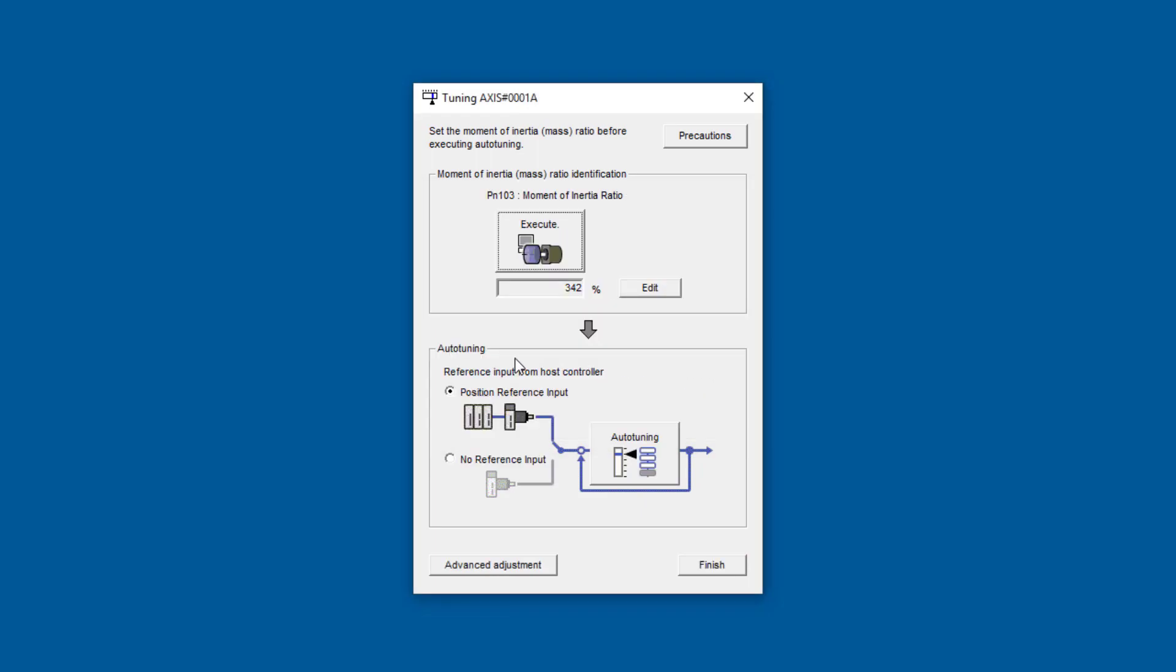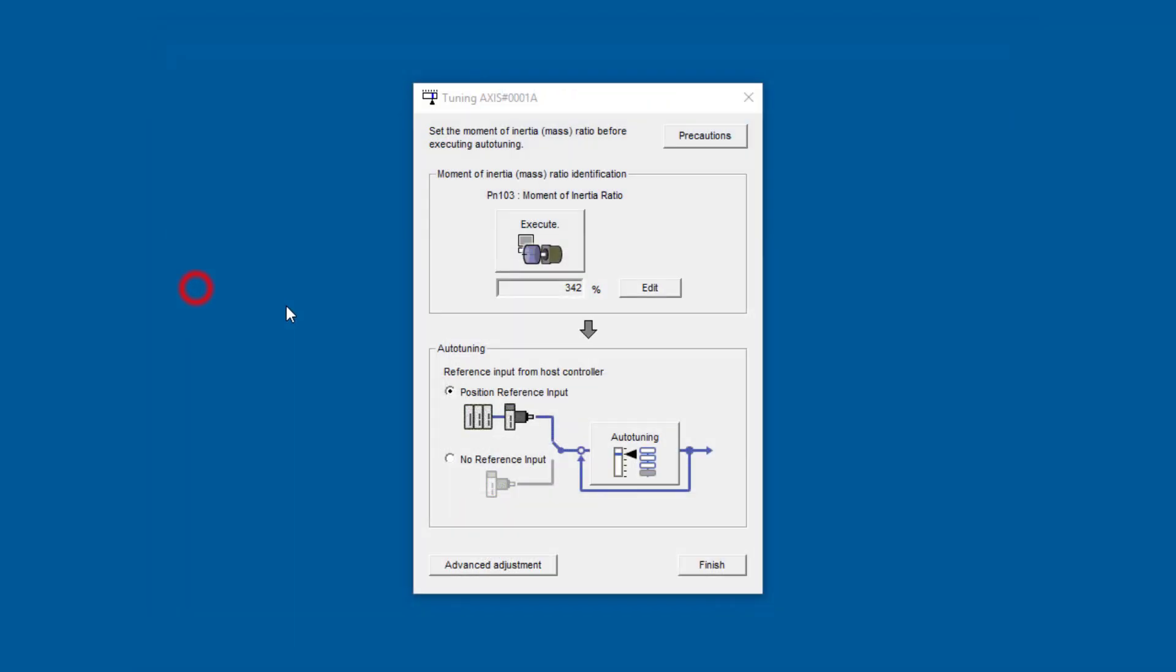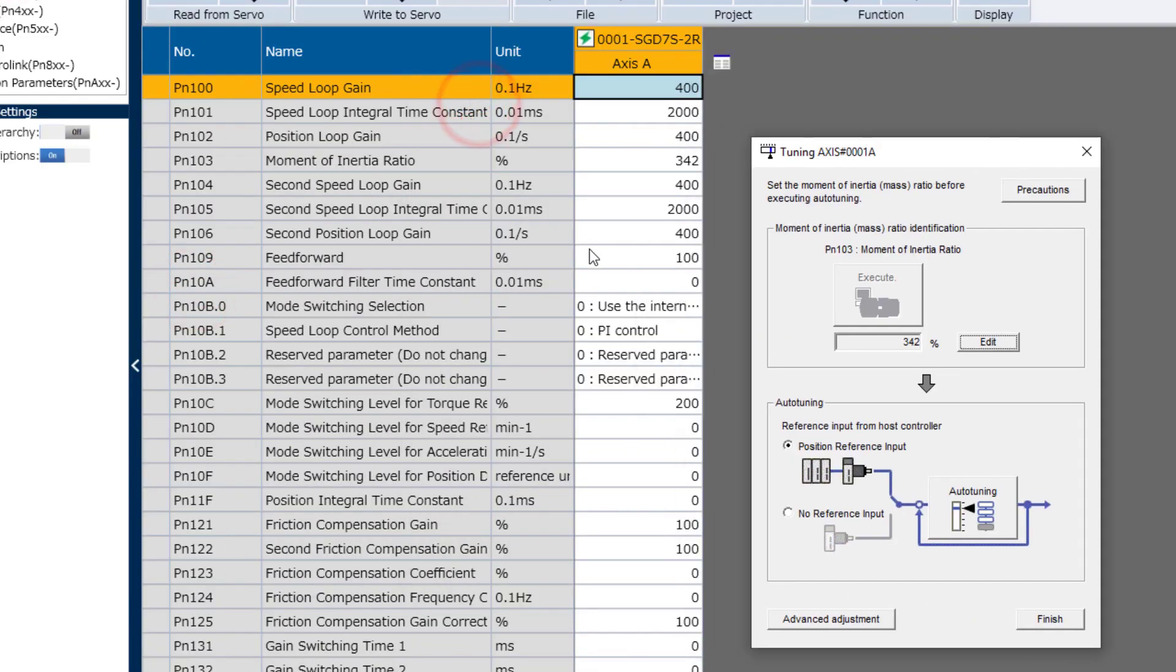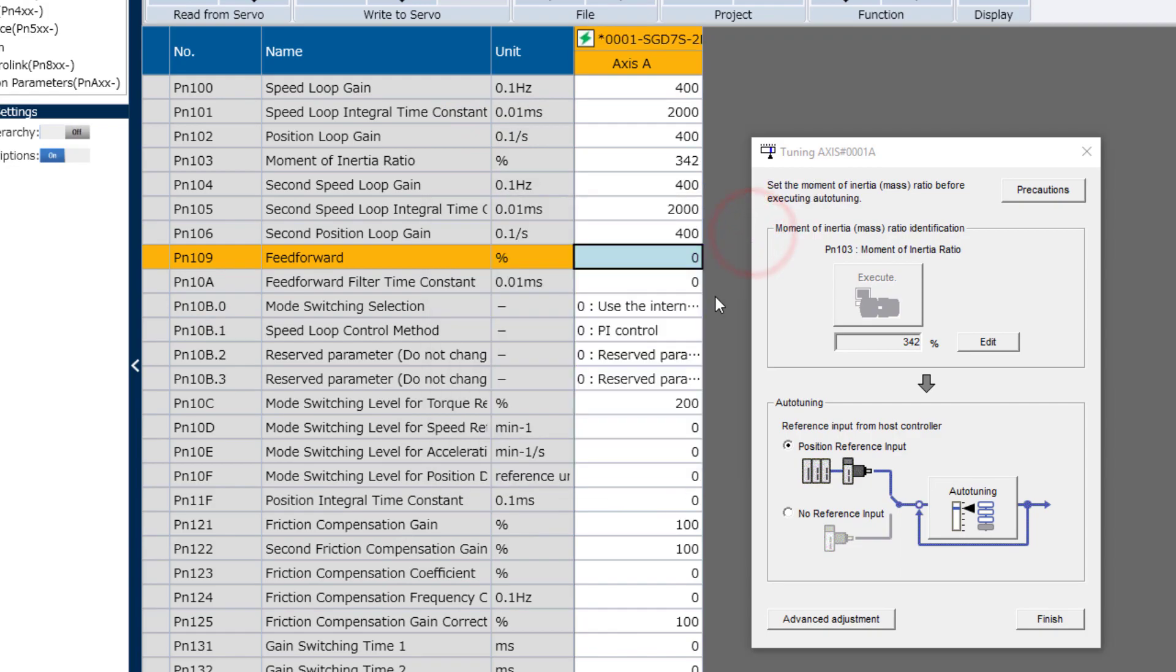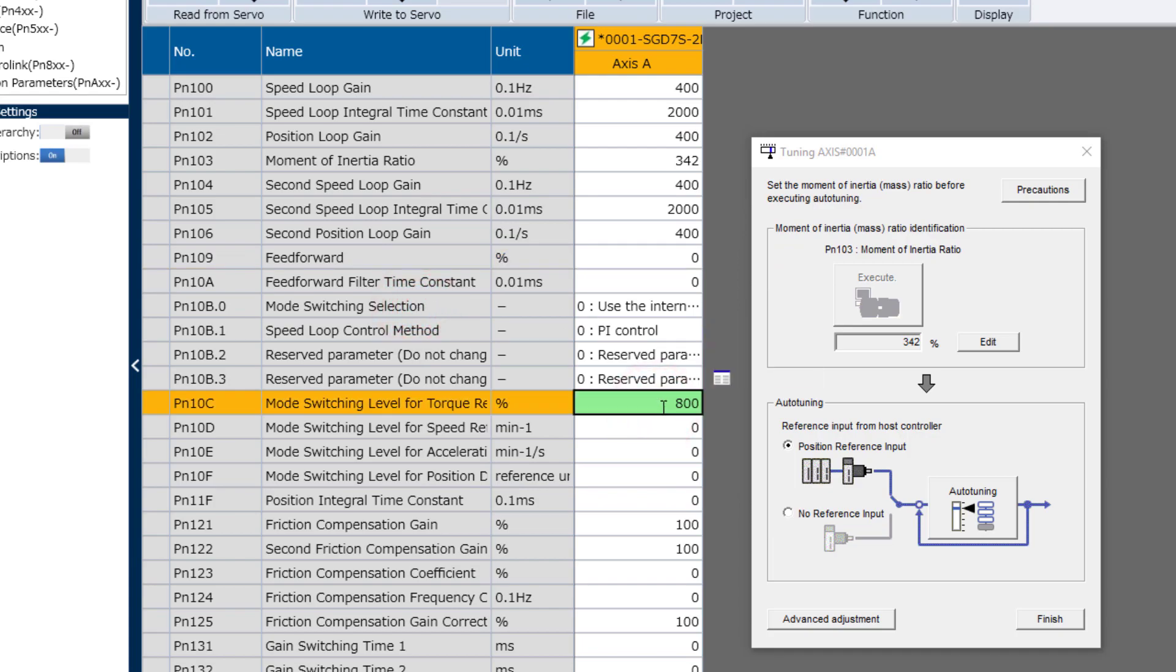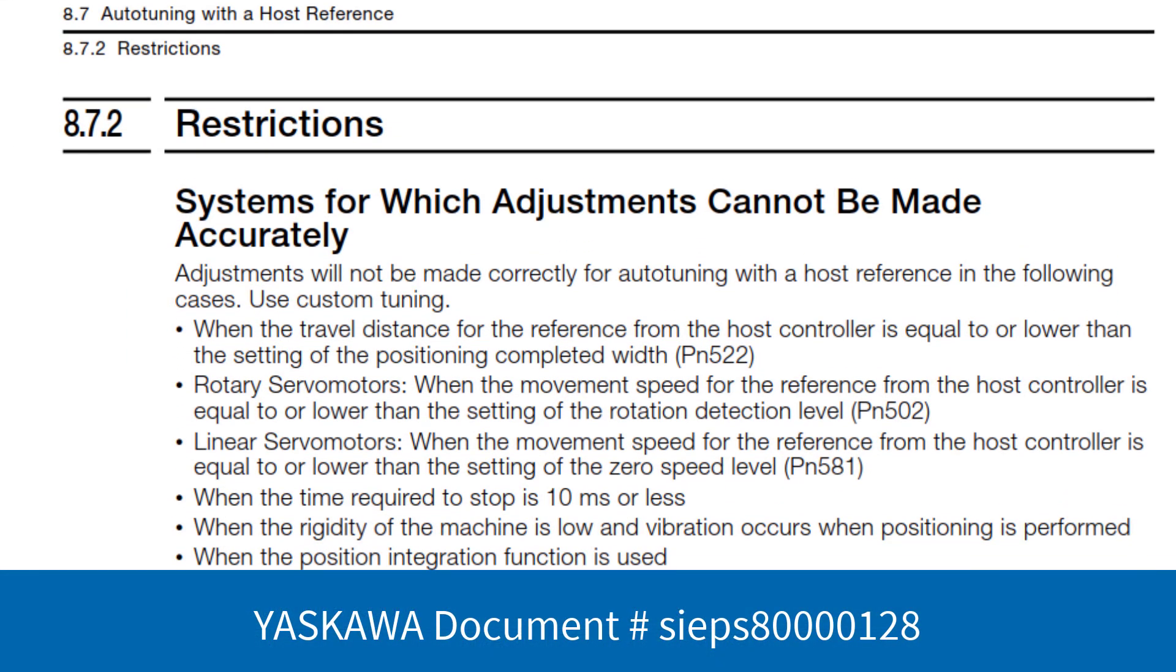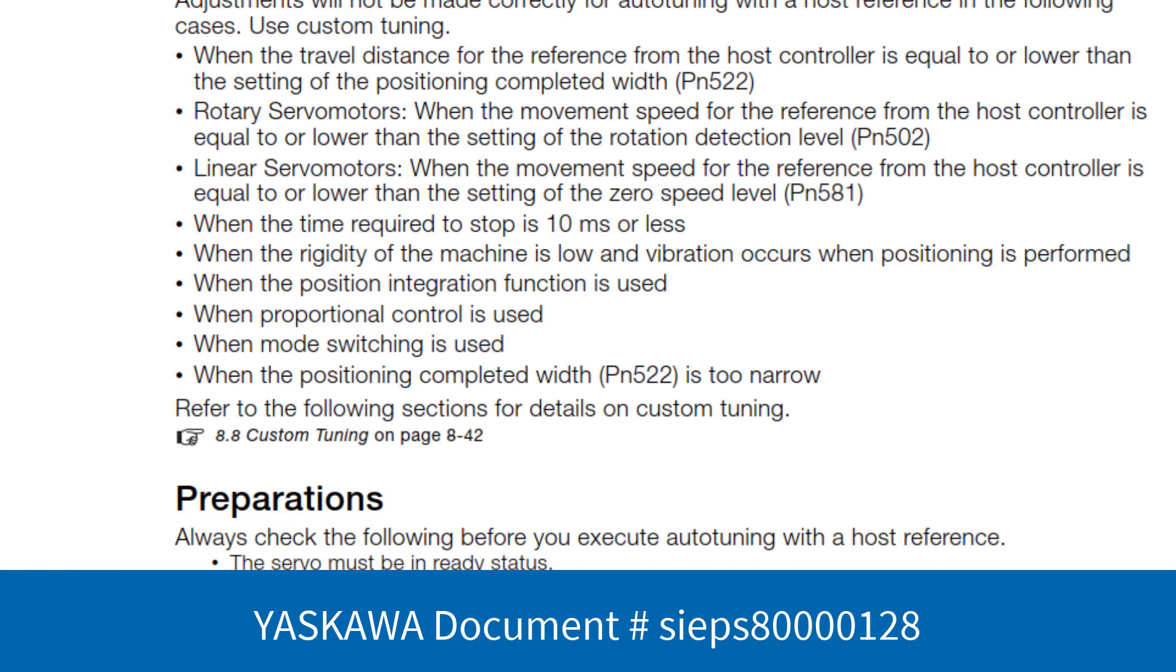Now a couple checks before you run Auto-Tuning, especially if it's going to be without model following control. First, go back to the parameters and be sure that you set PN109 back to the default of 0. Write that in here. It's also recommended to set the mode switch torque level up to max beyond the capacity of the motor. And in fact, there are a number of preliminary checks for Auto-Tuning listed in the manual.